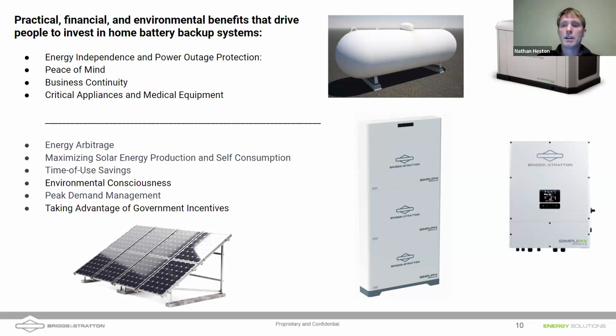The other thing about battery and inverter systems is, right, they do offer you a payback. You can make your money back on them. Once you spend your money on a generator, you have to pay for the fuel, and you're not going to get paid back by using that fuel to generate your own electricity. Typically, kilowatt hours generated by a generator system, even a high efficiency one, are much more expensive than the kilowatt hours you pull from the grid. So they're almost strictly for backup use, because financially it doesn't make sense.